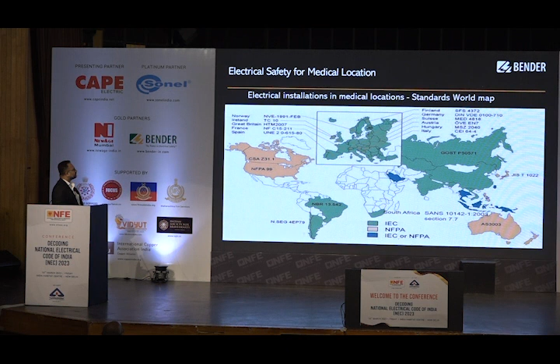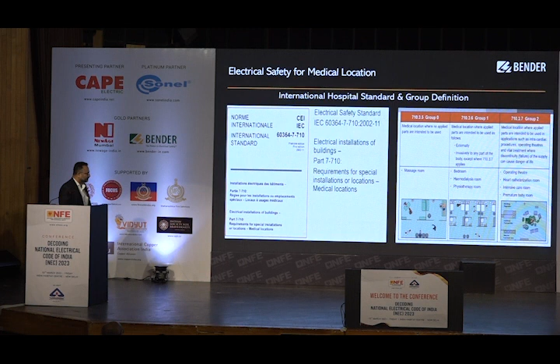This is the IEC standard. The basic requirement is that it categorizes the entire hospital into three different zones: group 0, group 1, and group 2. Group 2 is the major critical zone, covering the operation theater, heart catheterization room, intensive care room, and premature baby room. Basically, wherever invasive equipment goes inside the skin is a group 2 location; other rooms are not as critical because no invasive surgical equipment is used there.